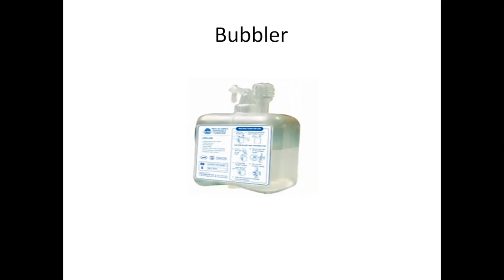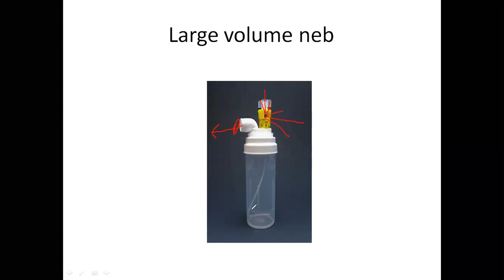This is a large volume nebulizer. This works off a Venturi valve. We'll fill water up in the cylinder there, and then that Venturi effect, as that gas shoots through there and creates a negative pressure and entrains more air, that gas is going to flow out this large 22 millimeter port in this direction here. This is our Venturi port. Remember Venturi effect. As that gas shoots down through this smaller orifice, it has to increase in velocity. That increased velocity creates a negative pressure, which draws additional gas in there, and in this case also draws humidity, where it mixes up in this chamber and passes out here to the patient.